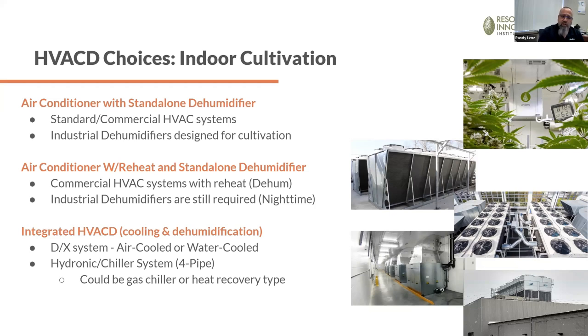Air conditioners really are designed to cool, to reject that heat, and as a byproduct they remove some water. In the residential world, that sensible heat ratio has really gotten down to about 85-15 - 85% of its energy is focused on removing heat from the space, and only 15% on removing water from the space. But there are differences by adding that heat back through hot gas bypass, or rejection of heat through a third coil. You can put some of that heat back into the space and get part of your dehumidification done that way.